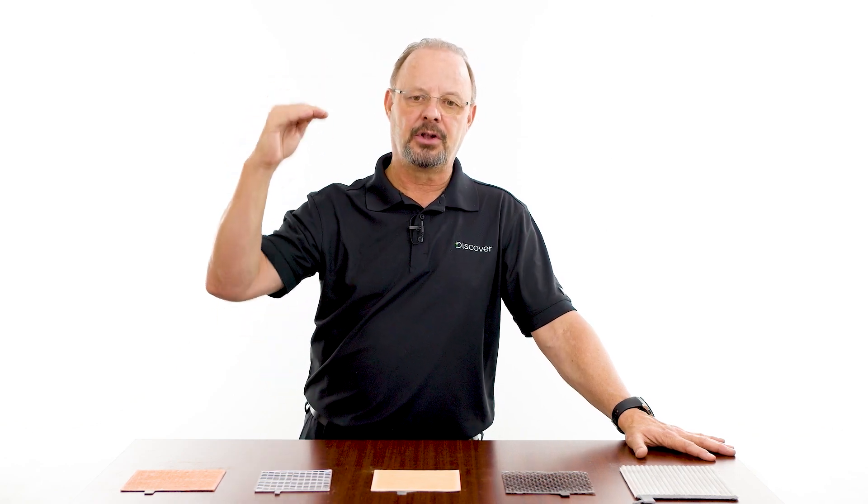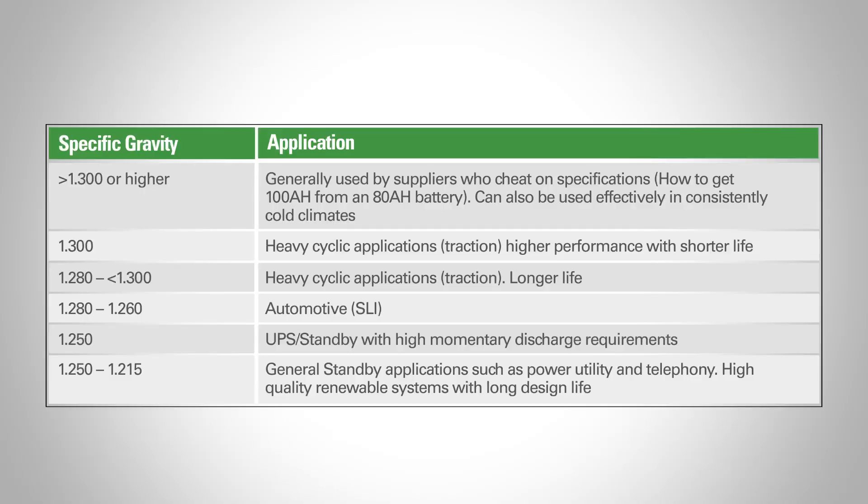If you use higher specific gravity, you can maintain that discharge for a longer period of time. But if you go too far, you'll over-discharge that battery and won't be able to discharge it very often. Suppliers using acid at 1330, 1350, or higher are essentially labeling a battery as 100 amp-hour when, more responsibly, a lower specific gravity should be used — producing a battery that lives longer but must be rated a little lower.